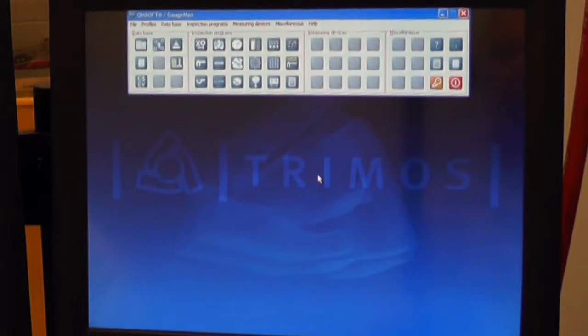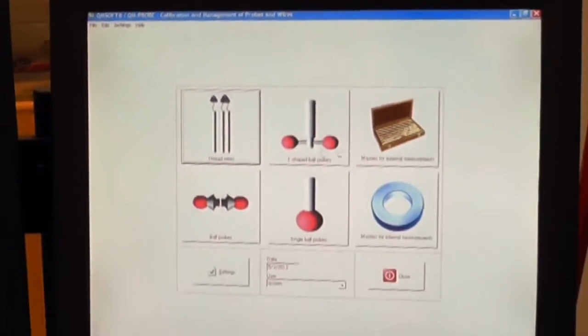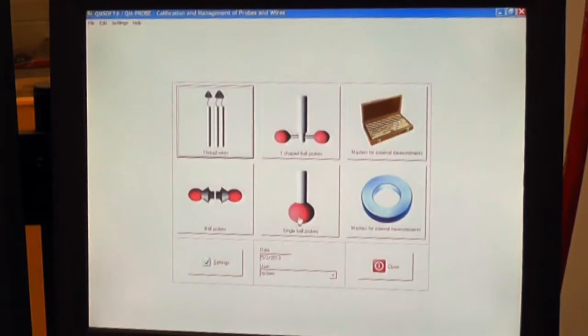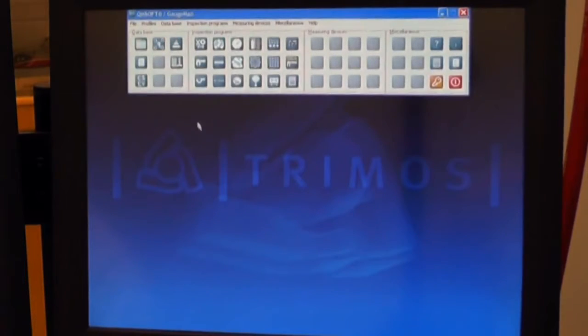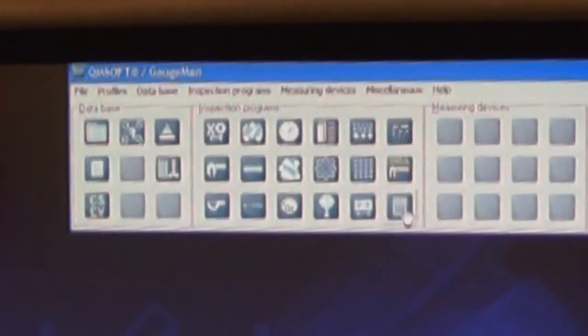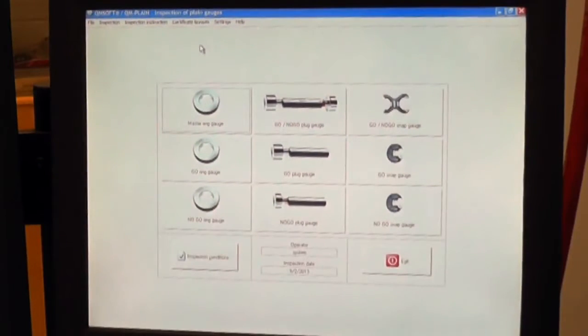On the top right, we have QMsoft, which is a gauge management software. This left section here contains databases for any measuring tools or probes, such as our T-shaped ball probes or single ball probes, any masters we use in the calibration of those. The next section over are the inspection programs. For example, this is your plain gauge section, where you have the measurement tools for ring and plug gauges as well as snap gauges.